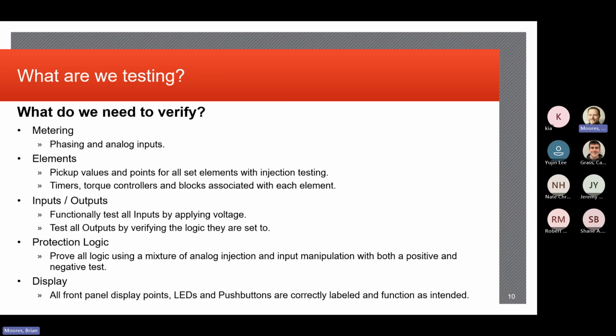So we're going to simulate those tests. Remember I said it looks at voltages and currents and makes decisions based on those. So we would want to make sure that we're looking at the metering quantities. So we're going to inject voltages and currents into the relay. And we're going to make sure that the PT ratios, CT ratios match what is shown on the drawings. So if we put in 5 amp secondary and the relay is set for a 2000 to 5 amp CT ratio, what should I see as primary amps in the relay? Or what would the relay see?